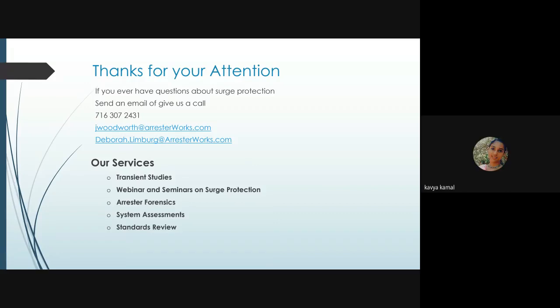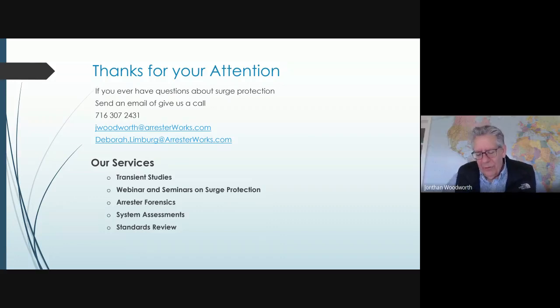Next one. How to protect high-rise buildings from lightning? Oh, not with arresters. That's a lightning rod. Now, the lightning protection systems that are used to protect tall buildings are really just ground wires. And sometimes, though, when the ground wires do carry high current from the top of the building to the bottom, it does pass by the power system. And indeed, this is why it's usually good to have small voltage SPDs on your TV and the different machines that you use in a home or in a high rise.